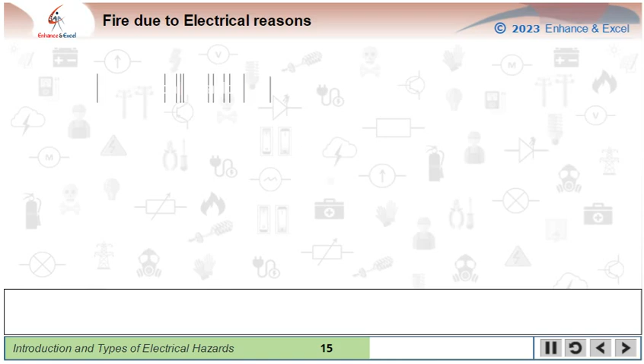Now let us consider the fires that start due to electrical reasons. The first one we consider is sparking. Whenever two electrical conductors with different potential touch each other intermittently, sparking is observed. You must have observed such arcing in day-to-day life. If fire load in close vicinity of electrical panels is high, it can catch fire and the situation may turn into a larger fire incidence.